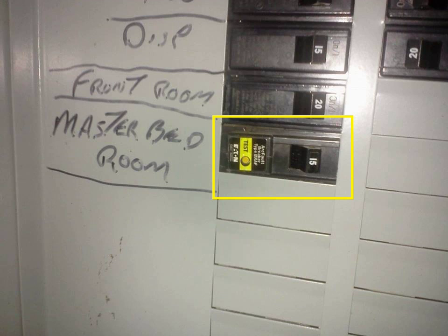Arc fault circuit interrupters located in receptacles are designed to prevent fires caused by glowing connections in wiring or panels. From the receptacle, an AFCI can detect the voltage drop when high current exists in a high-resistance junction. In a properly designed and maintained circuit, substantial voltage drops should never occur. Proper wire terminations inside utilization equipment, such as appliances and cords, prevent high-resistance connections that could lead to fires.